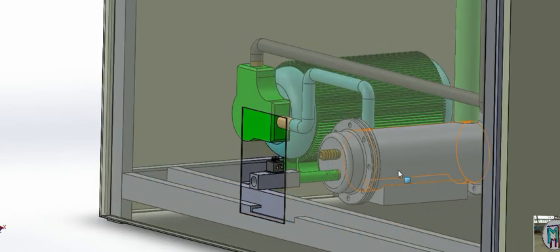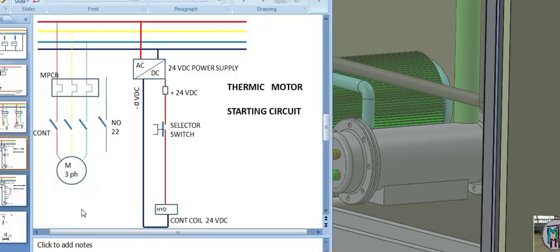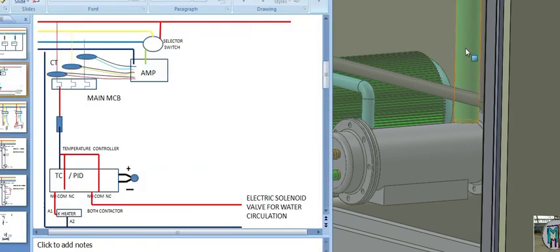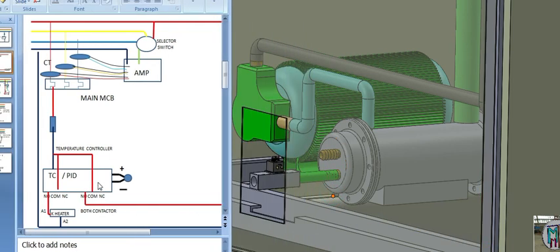We have to describe here that when your temperature has not reached the set point, suppose you have set 40 and the temperature of the tank is around 25, at that time the heater will be on. And when the temperature increases and reaches 45, because you have put new material in your tank and we heat your material when we load it, the temperature will increase, and at that time we need to start our cooling system. At that time your electric solenoid valve will be operated through this PID, and this valve will operate, and circulation will be here.